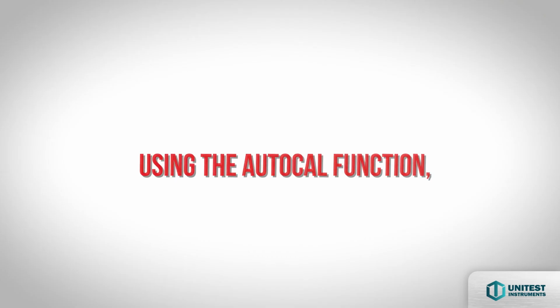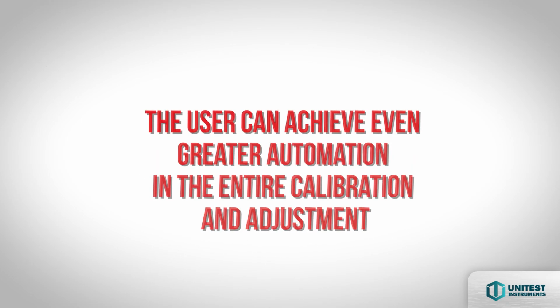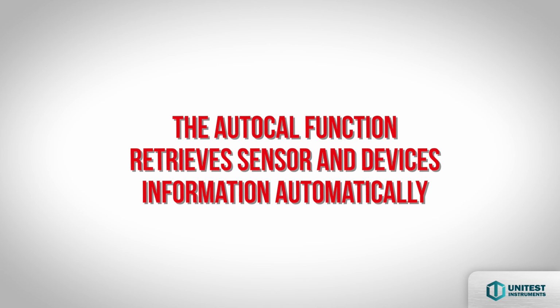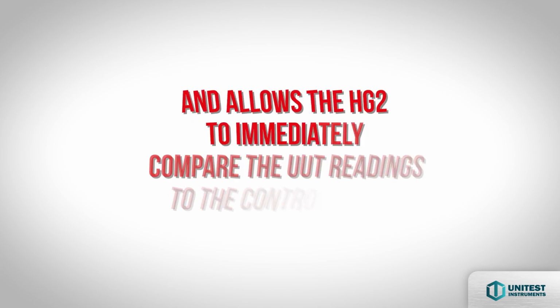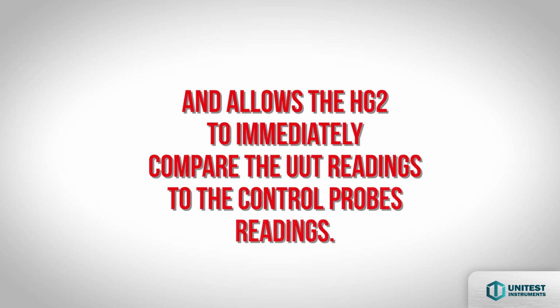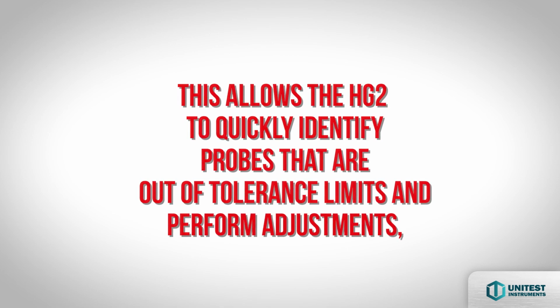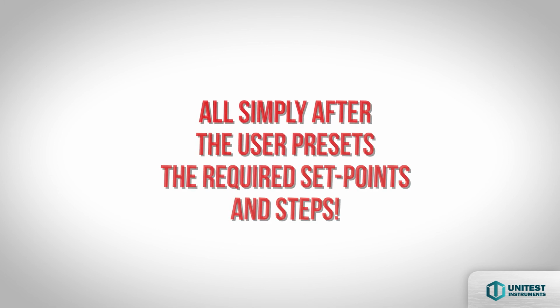Using the AutoCal function, the user can achieve even greater automation in the entire calibration and adjustment. The AutoCal function retrieves sensors and devices information automatically and allows the HG2 to immediately compare the unit under test readings to the control probe readings. This allows the HG2 to quickly identify probes that are out of tolerance limits and perform adjustments, after the user presets the required set points and steps.